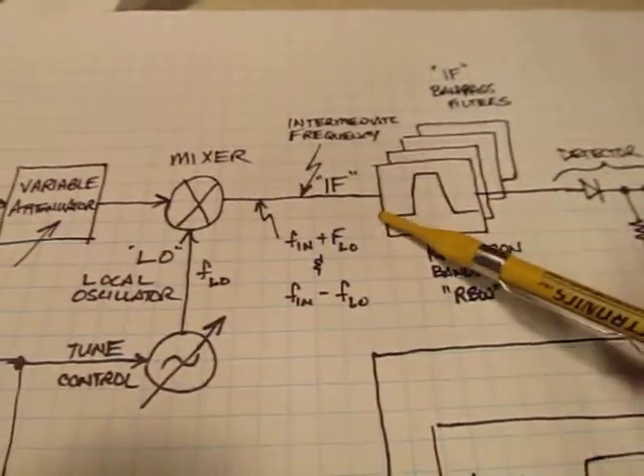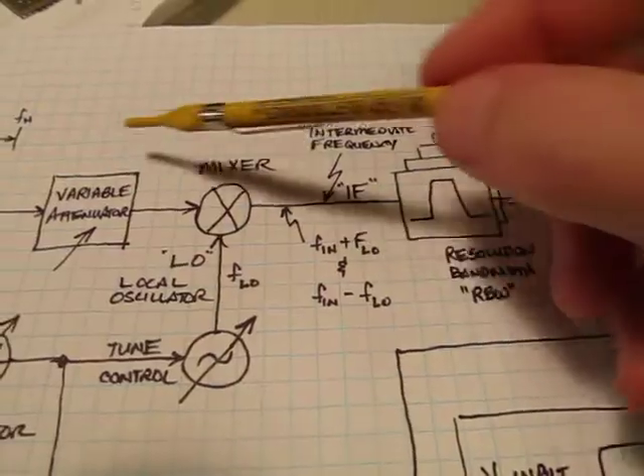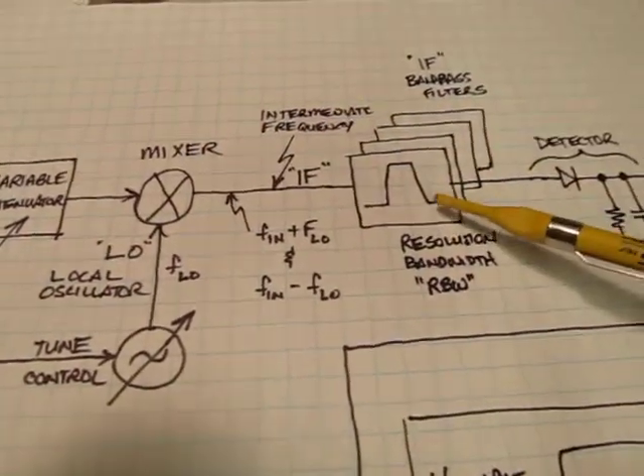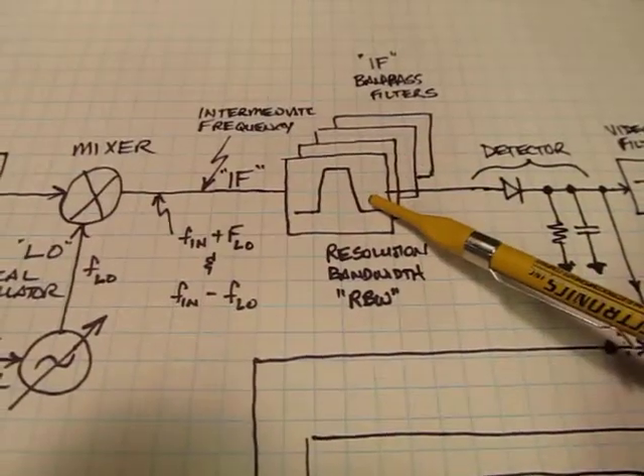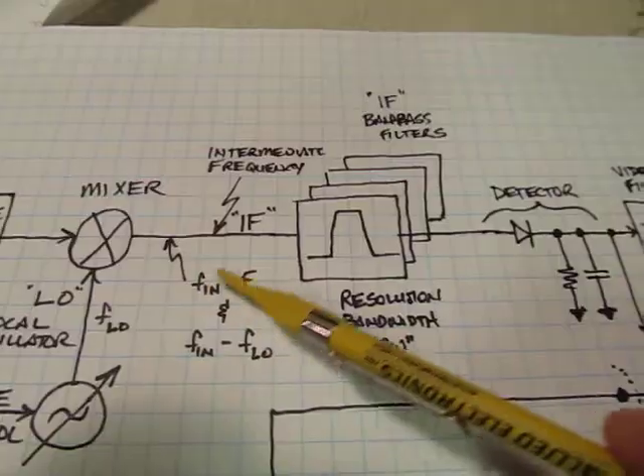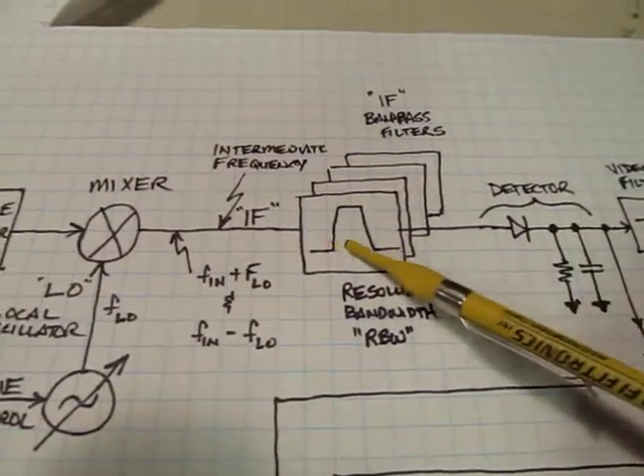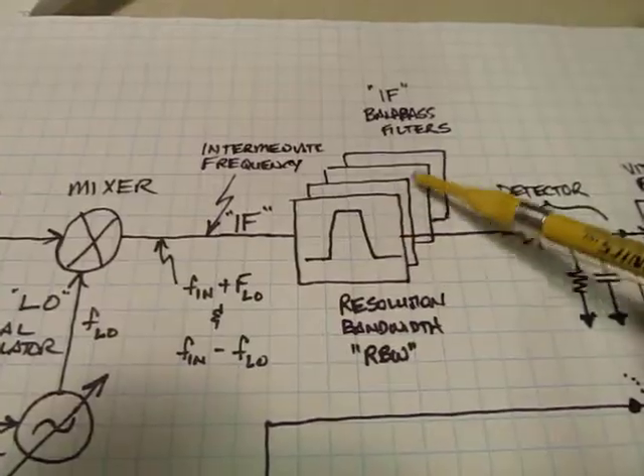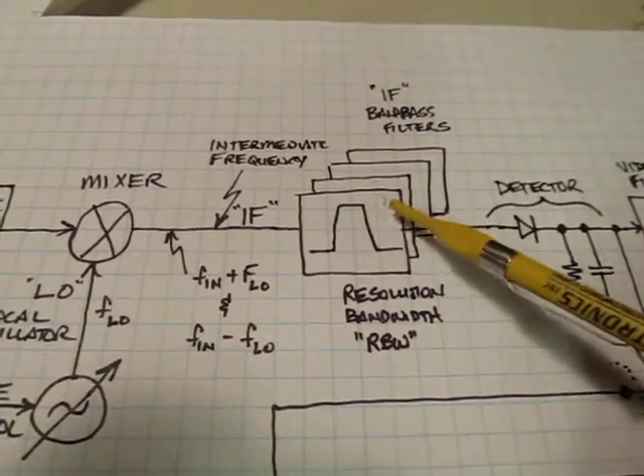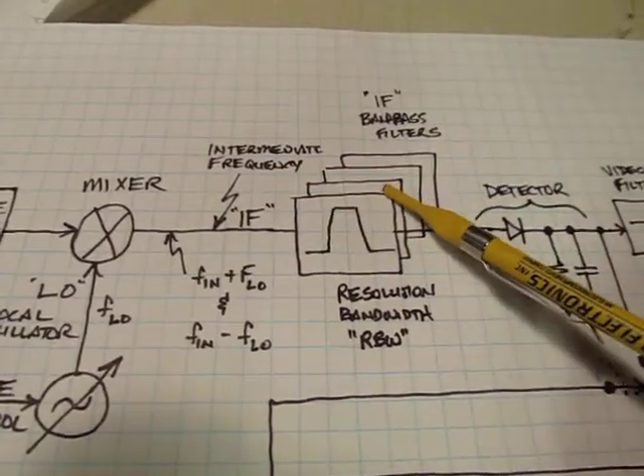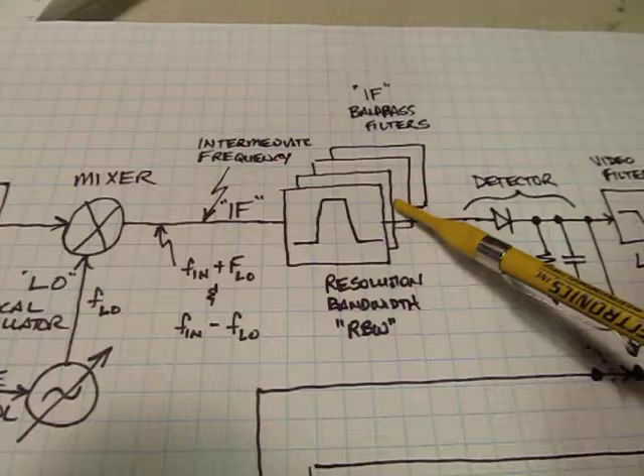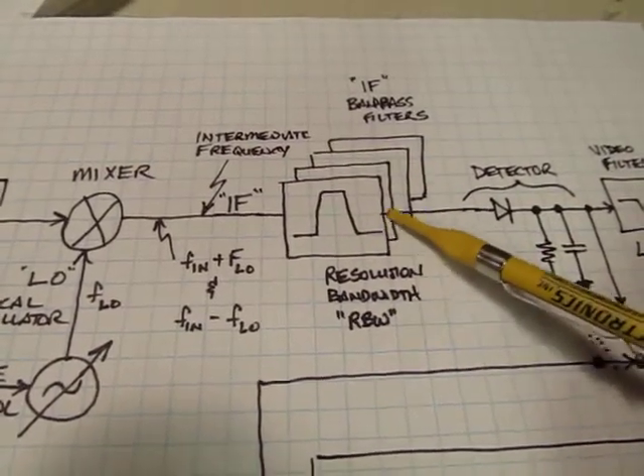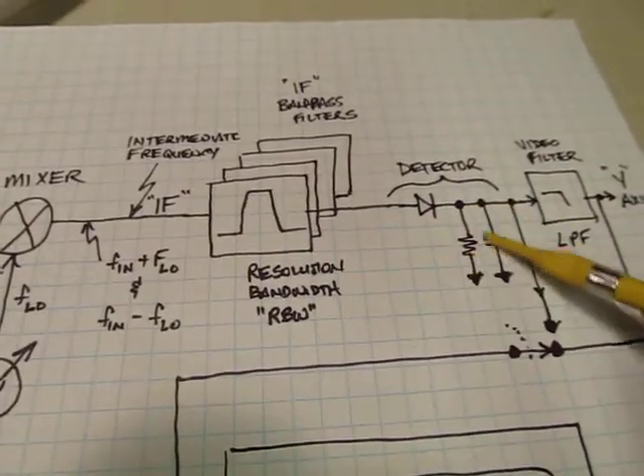And therefore, the IF is really not changing. We're just changing what lands in there from the mixer. And then the resolution bandwidth is kind of like the filter that you have on your radio receiver. When you tune to a particular station that you're listening to, you're not hearing the station below it or above it because you're only hearing what's passing through this filter. Typical spectrum analyzers have a number of different filters that have different widths. That makes it easier to resolve very closely spaced signals, which is why we call this a resolution bandwidth or it's typically called an RBW filter.